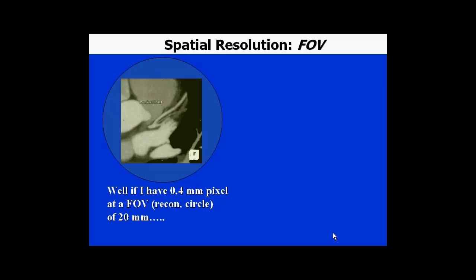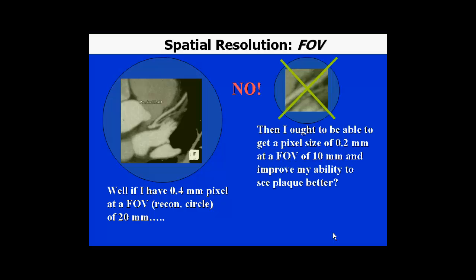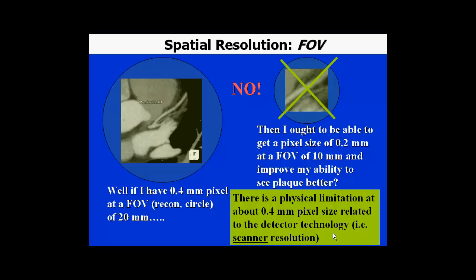Many people ask whether reducing the field of view further — say to 10 millimeters — could yield pixel sizes as low as 0.2 millimeters, improving visualization of the coronary artery and plaque. However, this is not possible because in multidetector CT there is a physical limitation on the lowest slice collimator setting, which is related to the resolution of the actual detector array. In general, the physical limitation is approximately 0.4 millimeters pixel size.